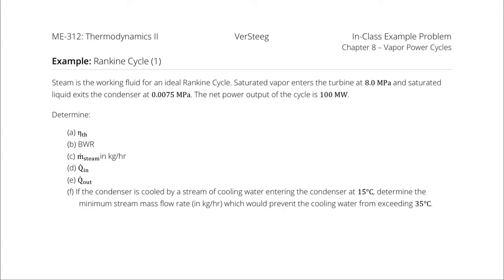Steam is the working fluid for an ideal Rankine cycle. Saturated vapor enters the turbine at 8 megapascals, and saturated liquid exits the condenser at 0.0075 megapascals. The net power output of the cycle is 100 megawatts. Determine the thermal efficiency, the backwork ratio, the mass flow rate of steam in kilograms per hour, the rate of heat addition, the rate of heat rejection, and if the condenser is cooled by cooling water entering at 15°C, determine the minimum stream mass flow rate in kilograms per hour to prevent the cooling water from exceeding 35°C.